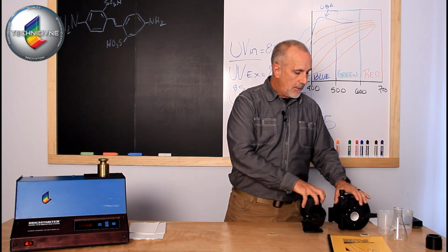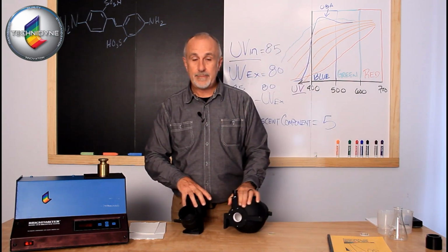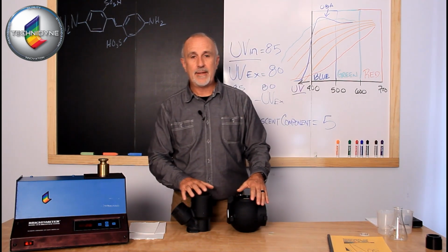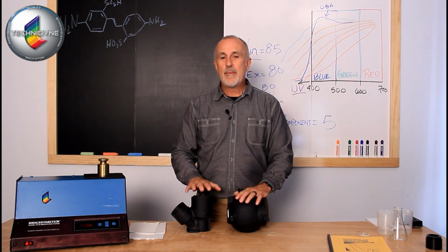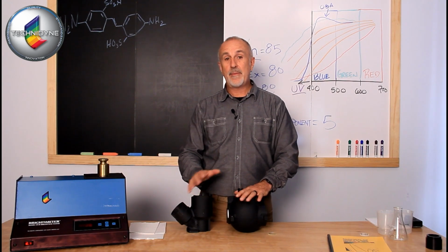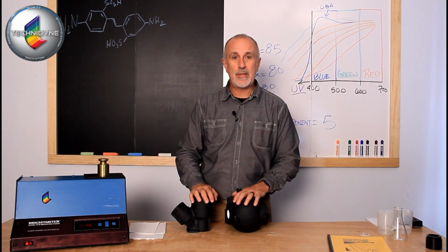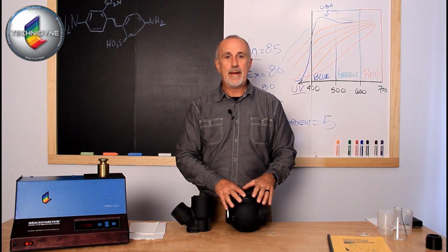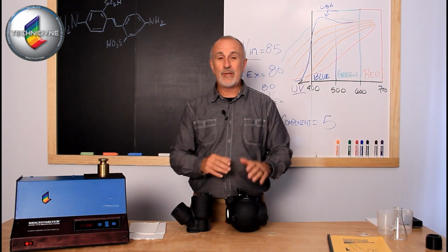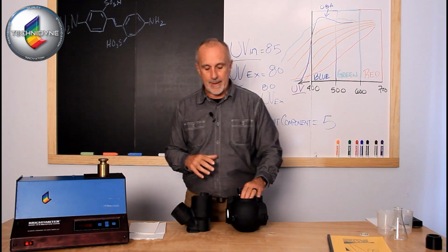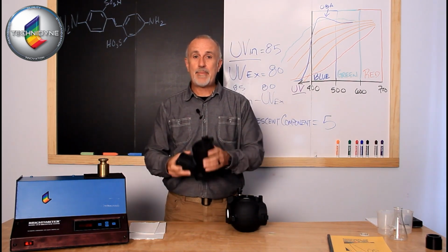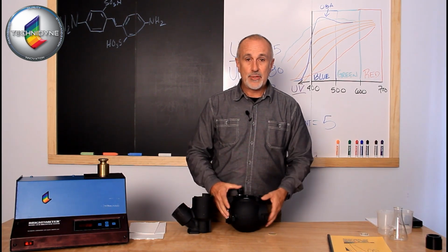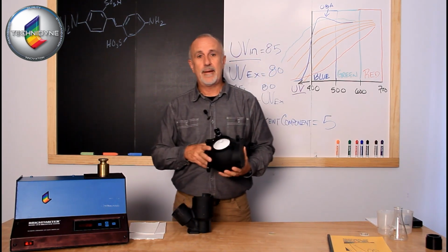Now, we've talked earlier in this video about TAPPI and ISO, and a lot of the things are the same. But there are some differences between these. If you watch the ISO video, you will see some of those differences, where this has some benefits of looking at different UV regions because of the pulse xenon flash lamp. But there are also some benefits to the TAPPI method that's important to understand as well, because they highlight things that you really have to pay attention to when you're using an ISO geometry.